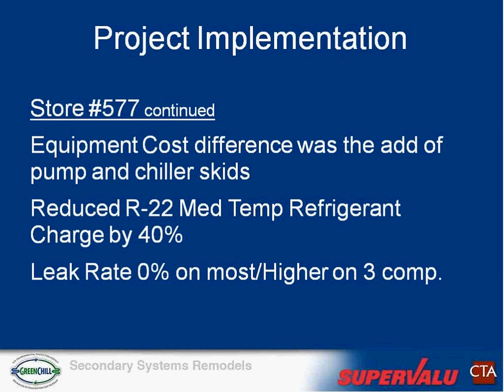on a couple of these compressors, since we reduced the charge so dramatically, the actual amount that we leaked was less than what we would have previously leaked with a small leak rate percentage. And part of the thing is we reduced our leak potential by eliminating all the piping and stuff out in the store where we can get a leak. We reduce our charge, which then, when we do have a leak, amounts to less refrigerant being released to the atmosphere. So we already tested it, and it proved to be beneficial in that area.